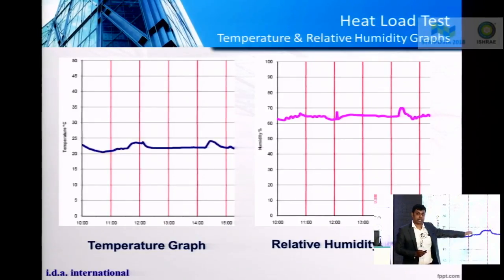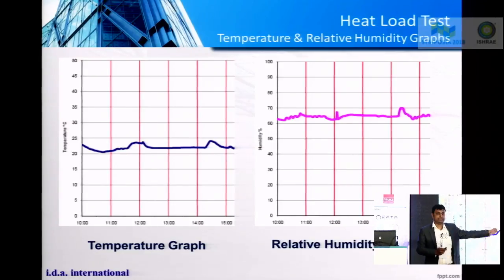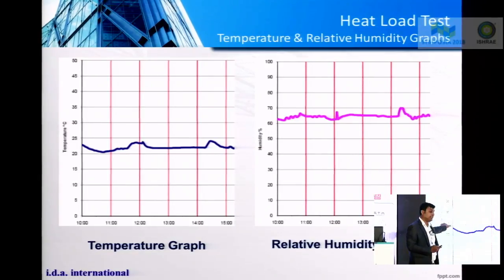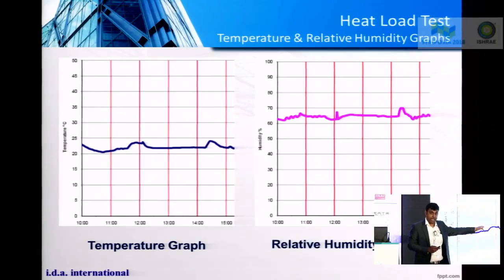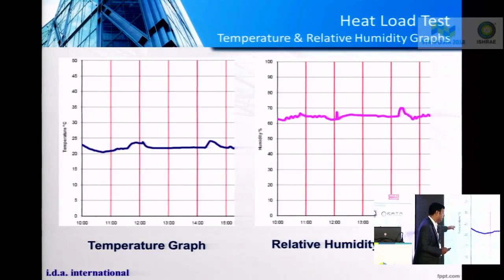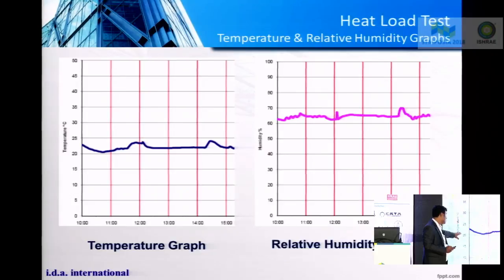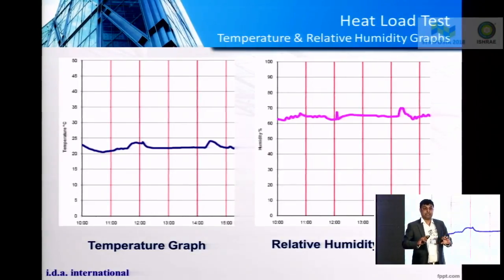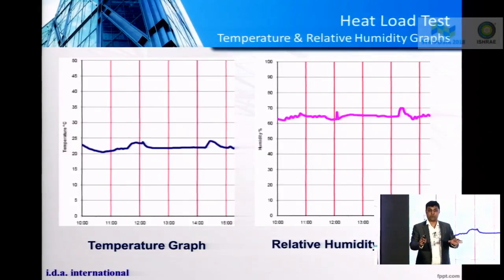how the temperature was across the data hall during all these scenarios, and I will verify that it was a fairly straight line and within your SLA limit. So here the temperature was between 20 and 25, which was within the SLA limit, so I can say that yes, the performance of the thermal conditions was within the acceptable limits. Same goes for relative humidity.